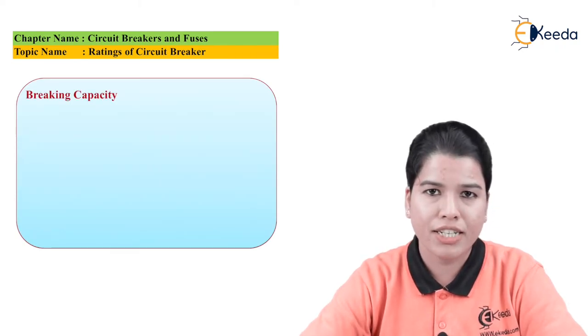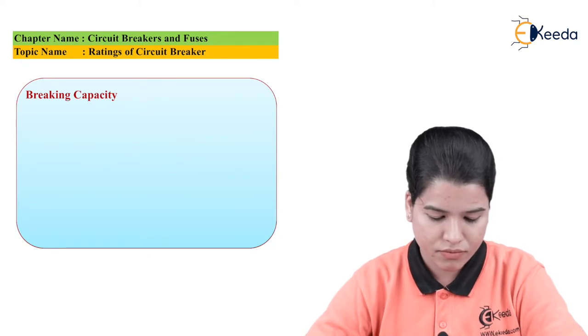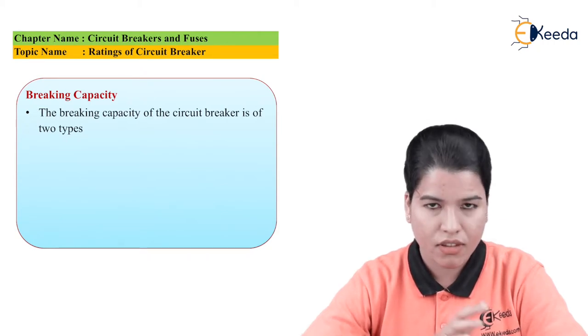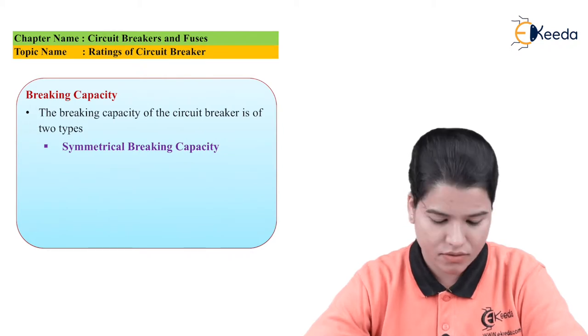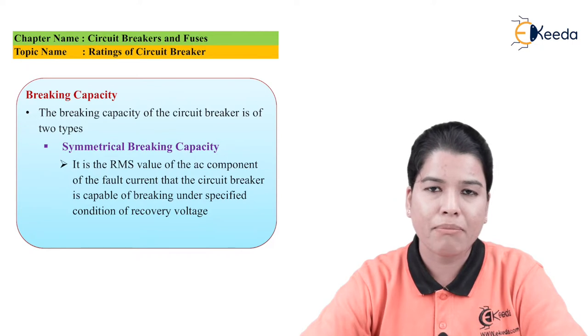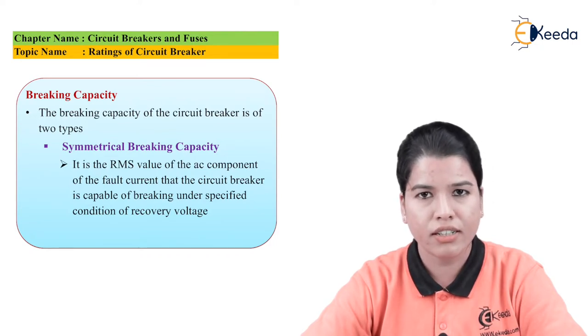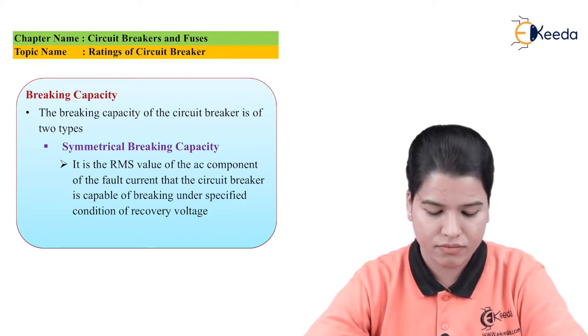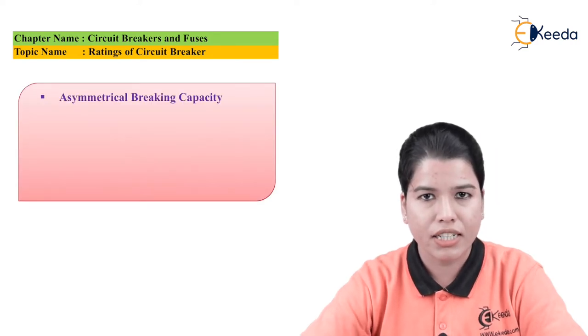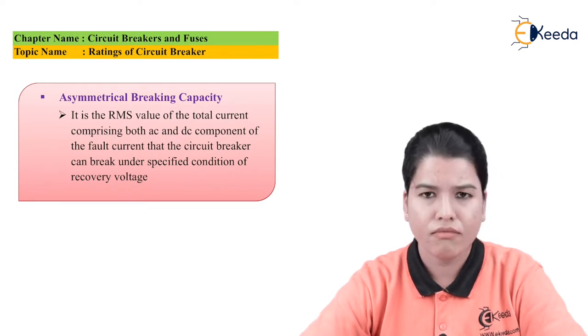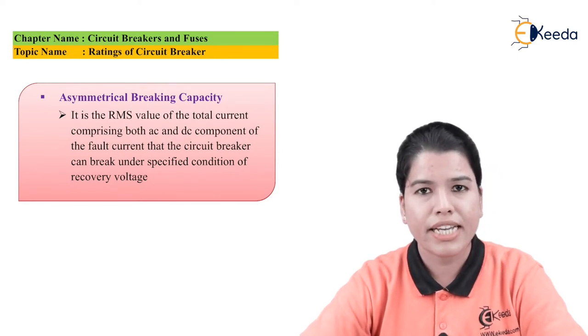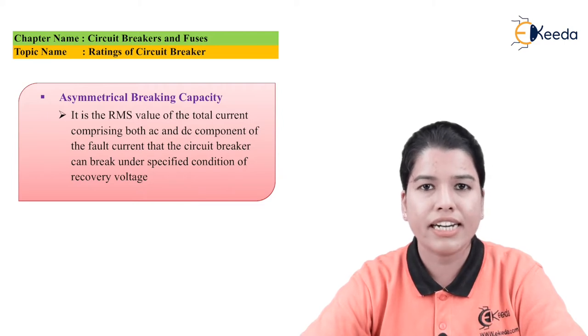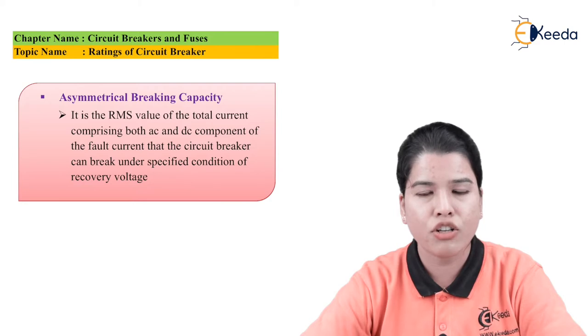The breaking capacity of a circuit breaker is classified into two types. First, symmetrical breaking capacity, which is the RMS value of the fault current that the circuit breaker is capable of breaking under the specified condition of the recovery voltage. Second, asymmetrical breaking capacity, which is the RMS value of the total current consisting of both the AC component and DC component that the circuit breaker is capable of breaking under the specified condition of the recovery voltage.